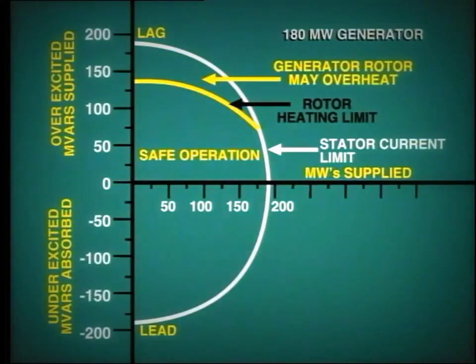This curve shows the limitation due to rotor heating. You can see that we can operate this generator at 180 megawatts and zero megavars. But if we needed to produce, say, 100 megavars, then we would have to reduce the active power output to 140 megawatts in order to keep within the established rotor heating limits.